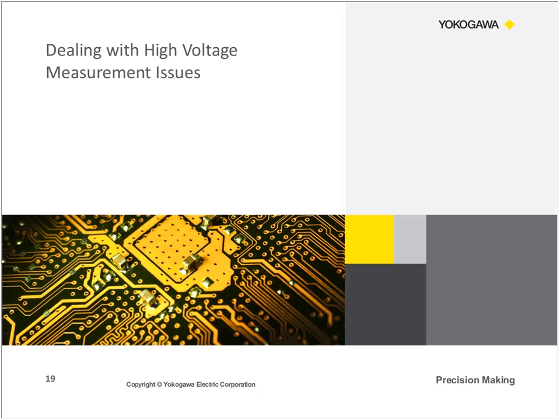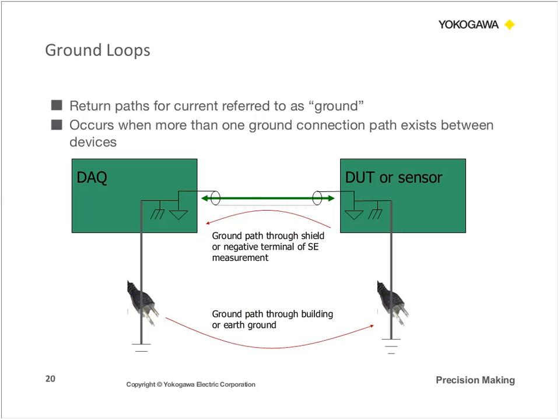So next we want to go into a little bit more detail about the issues that we presented earlier. And this was, as you can recall, ground loops, common mode voltages or noise, and how we can remove them by means of isolation. So ground loops are the most common noise problems in large-scale electrical systems, and as we mentioned earlier, they stem from poor grounding practices. A common misconception that beginning engineers have is that the earth ground at one location is going to be the same as the earth ground at a different location, but that's really not the case.